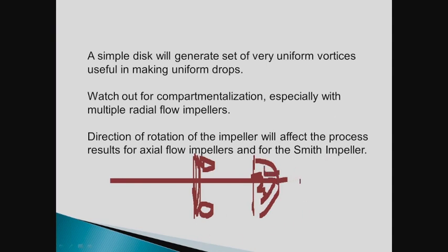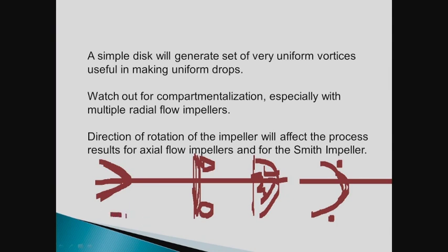Now then, the reason why the curved blades work so well is you have still the vortex up here and the vortex up there, but this bowing in here prevents these things from getting together and forming a large cavity. In fact, some designs are rather very cupped like that. I think the Scaba design looks like that. Some designs are. This could actually be very similar to the famous Arrowhead impeller.